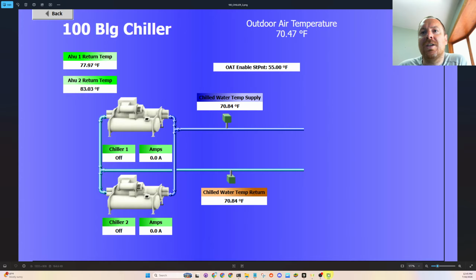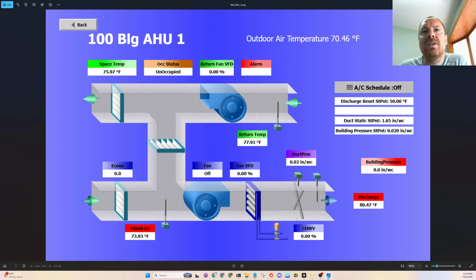I'm dying to know, when the maintenance department runs this building, like we've talked about before, if someone had to modify this discharge air temperature set point down to 50. Usually the design cooling leaving air temperature of the air handling unit is always 55, and then you float that up in the winter. They do that for dehumidification, for a design of 55 degrees.